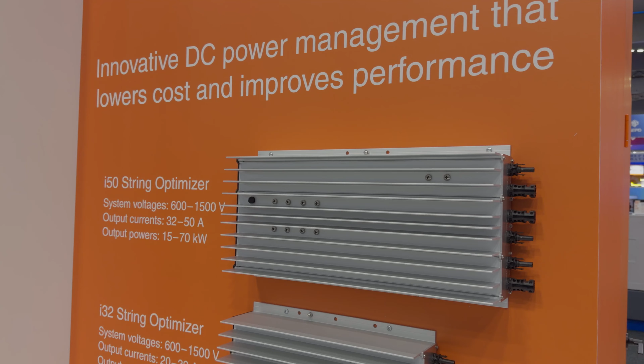What we do is put them at the string level and mount them to the torque tubes of the racking solution or the pylons, either fixed tilt east-west racking or a dual axis tracker system, right down at the PV modules. By doing so, we get maximum power point tracking and mismatch loss correction for degradation of solar modules, as opposed to dealing with it at the centralized level, which could be 200 meters away with many more losses, not addressed right at the modules where they need to be.